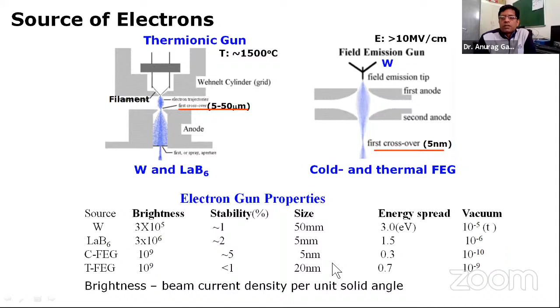So this is the table of the different types of guns being used for these systems: tungsten, with its source size, then LaB6, lanthanum hexaboride, Schottky field emission, and cold field emission. So this is the source size, then how much temperature they generate, then the brightness, the energy spread across the beam, the probe current, and the gun vacuum, that is, how much vacuum is required in these guns. In Schottky and cold field emission, they have 10 to the power minus 9 torr or 10 to the power minus 11 torr.